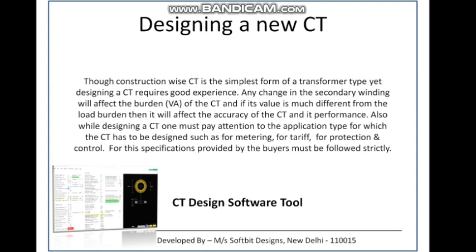Designing a new CT — though construction-wise a CT is the simplest form of transformer type, designing a CT requires good experience. Any change in the secondary winding will affect the burden of the CT, and if its value is much different from the load burden, it will affect the accuracy and performance. Also, while designing a CT, one must pay attention to the application type — metering, tariff, or protection and control — and specifications provided by the buyers must be followed strictly.